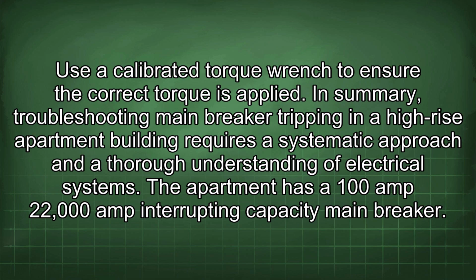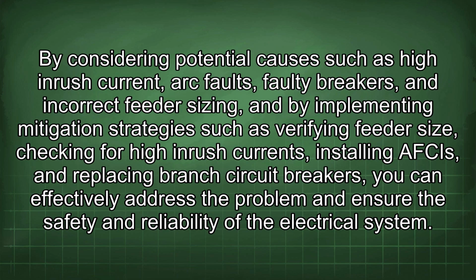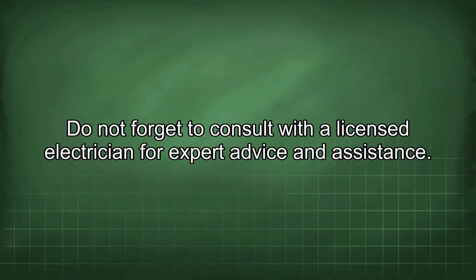In summary, troubleshooting main breaker tripping in a high-rise apartment building requires a systematic approach and a thorough understanding of electrical systems. The apartment has a 100 amp, 22,000 amp interrupting capacity main breaker. By considering potential causes such as high inrush current, arc faults, faulty breakers, and incorrect feeder sizing, and by implementing mitigation strategies such as verifying feeder size, checking for high inrush currents, installing AFCIs, and replacing branch circuit breakers, you can effectively address the problem and ensure the safety and reliability of the electrical system. Do not forget to consult with a licensed electrician for expert advice and assistance.